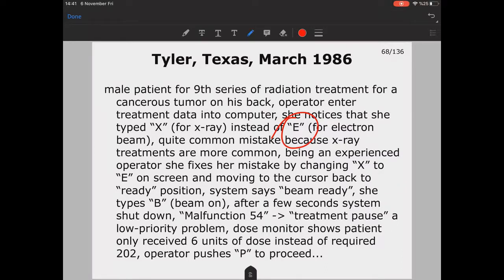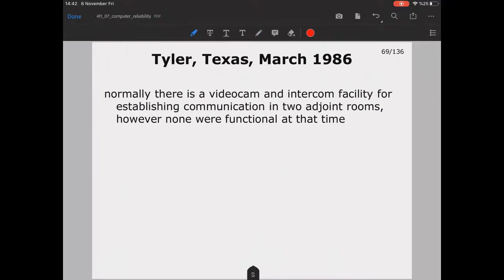The system says beam ready. She types B, beam on, and after a few seconds the system shuts down. Malfunction 54. Okay, treatment pause, a low priority problem which happens over and over again during the day. The monitor shows that the patient only received 6 units of dose instead of the required 202. So the operator types P again to proceed.